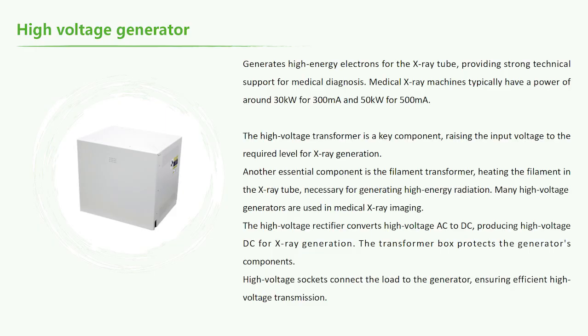The high voltage transformer is a key component, raising the input voltage to the required level for X-ray generation. Another essential component is the filament transformer, heating the filament in the X-ray tube, necessary for generating high energy radiation. The high voltage rectifier converts high voltage AC to DC, producing high voltage DC for X-ray generation. The transformer box protects the generator's components. The high voltage sockets connect the load to the generator, ensuring efficient high voltage transmission.